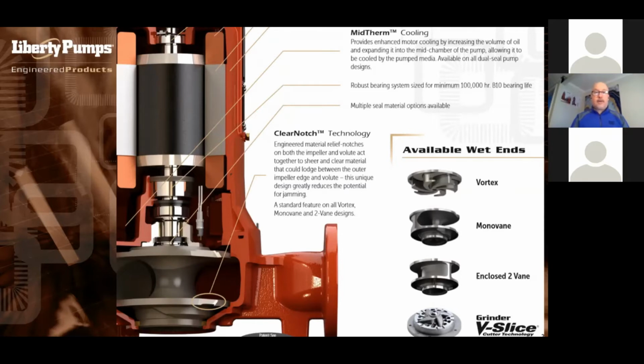Robust bearing design, meaning that we are using 100,000 hour rated bearings, a B10 bearing life. Other manufacturers will sometimes use a 50,000 hour rated bearing, so we write that into our specification. And then the multiple seal materials are basically the tungsten carbide option.